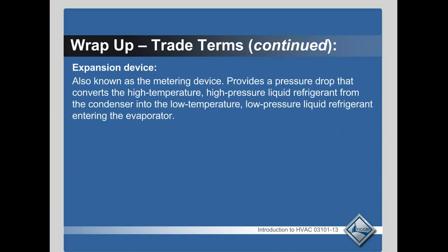The expansion device — this is the other dividing point which divides the high side of the system from the low side of the system. It provides a pressure drop, and whenever you have a pressure drop in refrigerant it lowers the temperature as well. So it takes that high pressure, high temperature liquid and drops the pressure down into the evaporator so that we can absorb the heat from the structure.